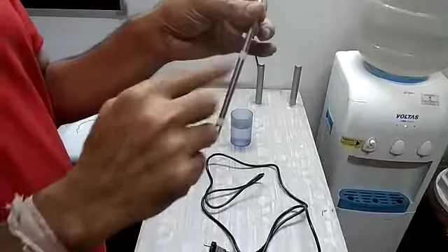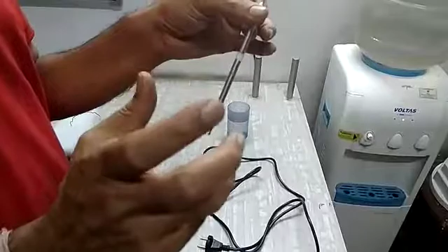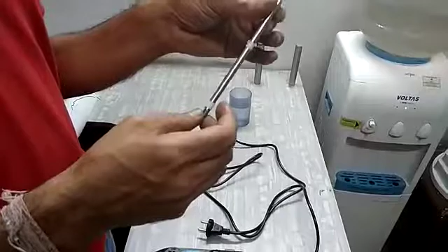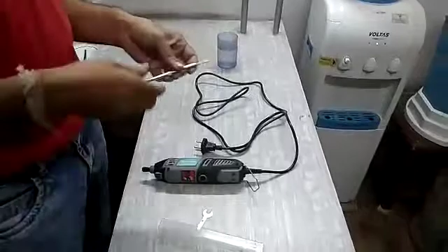One is the outer part, and this is called the stator, and the inner part is called the rotor. In this rotor there are two sleeves, and these are called fluorocarbon sleeves. With time and use these sleeves go bad, and we have to change them. The best indication is that once the sleeves are going bad, you will observe a lot of vibrations in your run. So maybe that is the time to change the sleeve, but it doesn't happen so fast, maybe after a year or so. So let us see how to run this machine and how to install the probes.